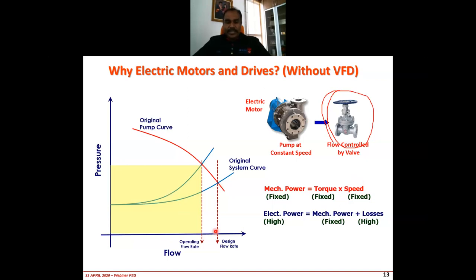Even though you reduce the flow by throttling the mechanical valve, you will notice that the mechanical power is about the same, because the pump and motor are still running at full speed. You don't do anything on the speed, the flow rate is controlled by the mechanical valve, and therefore there is not much change in the speed and torque. You might even have more losses because the pump is running at full speed. So there is not much reduction in electrical power. It is almost the same whether you operate at this flow rate or this one. This is what will happen.